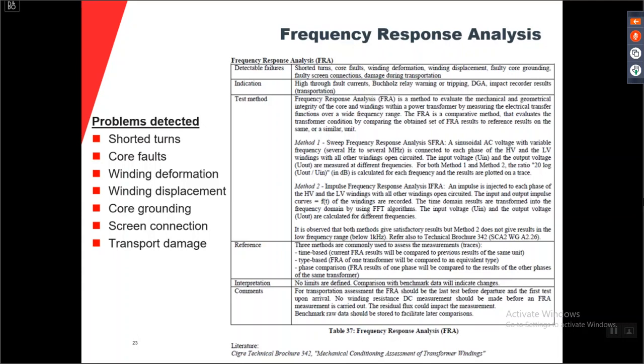Do you remember from part 1 when we looked at the short circuit impedance? If we found that the short circuit impedance didn't give a clear response, they said maybe you should do an SFRA test, or sorry, an FRA test, because it is a little bit more clear in finding different faults. The short circuit impedance defines that the transformer behaves as it should be doing, or as it did in the factory, but the FRA test can find faults a little bit easier, and it will see that something is happening earlier.